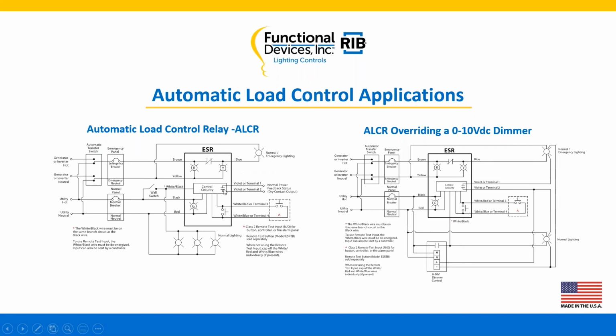So what's happening is when normal power drops off, emergency power kicks in. You notice this relay here in the center. It's a normally closed relay. What we are doing there is creating the power path for that power to get to that emergency fixture. Down here in the middle, you notice it says violet or terminal 1, violet or terminal 2. Basically, that would be where the 0 through 10 override would be attached. You notice it is open, there's nothing there.